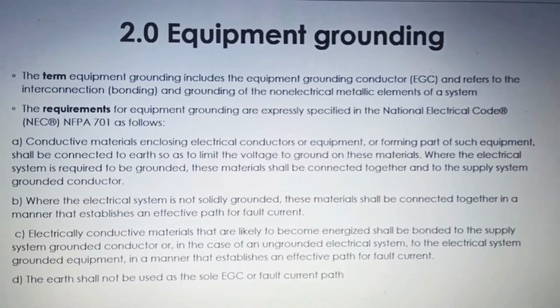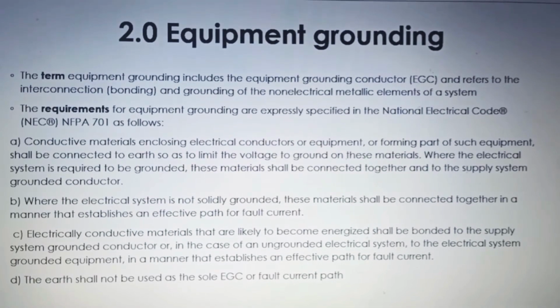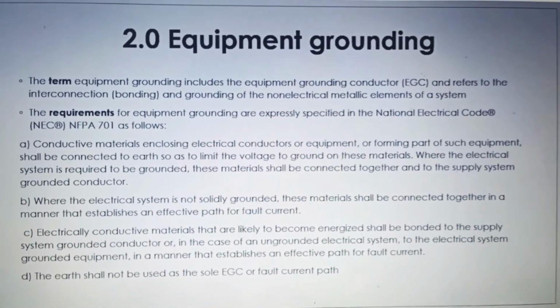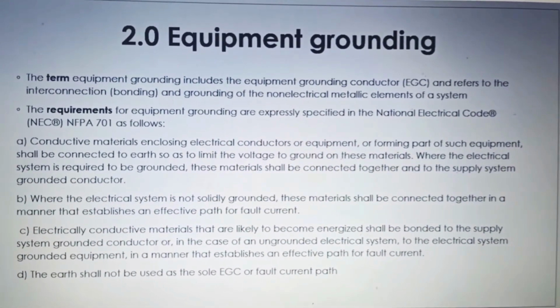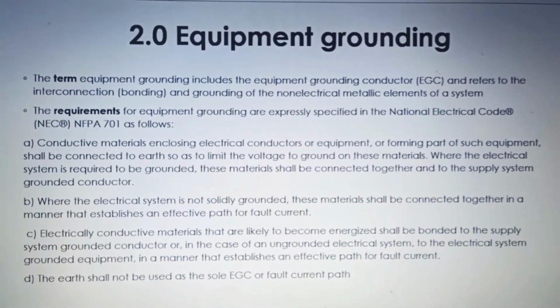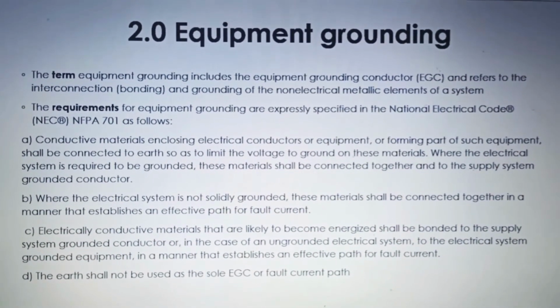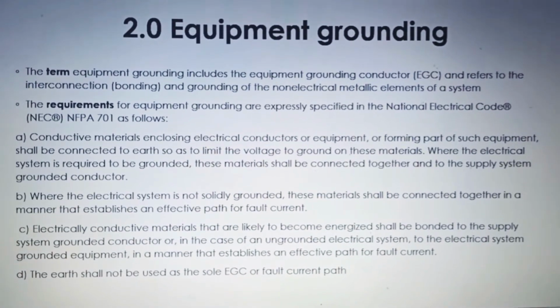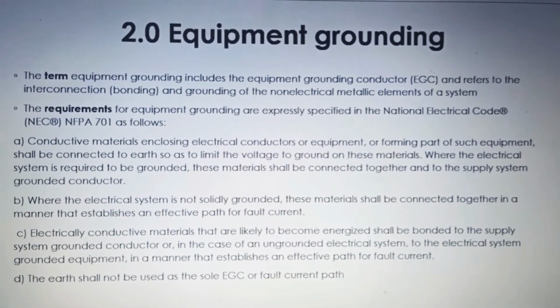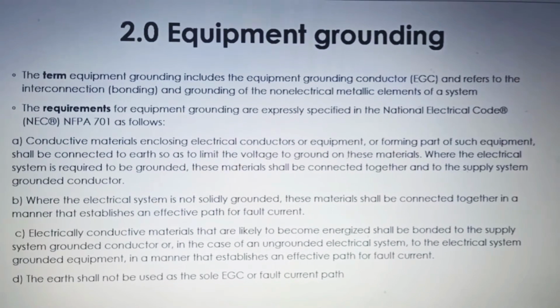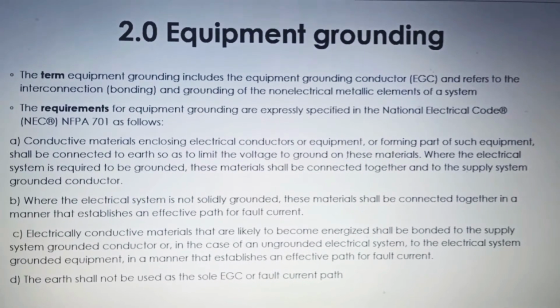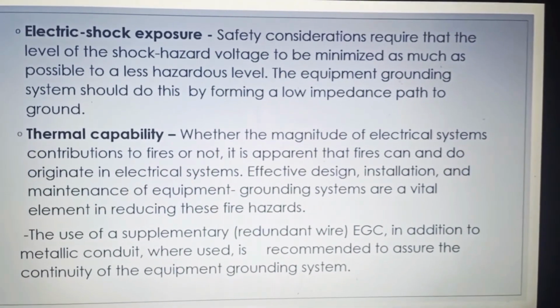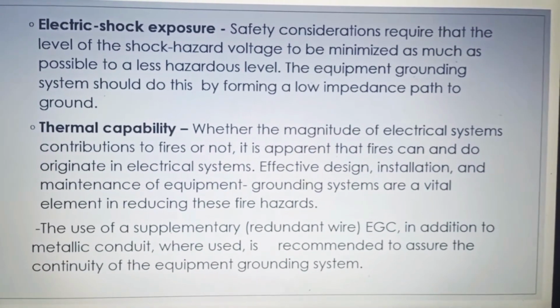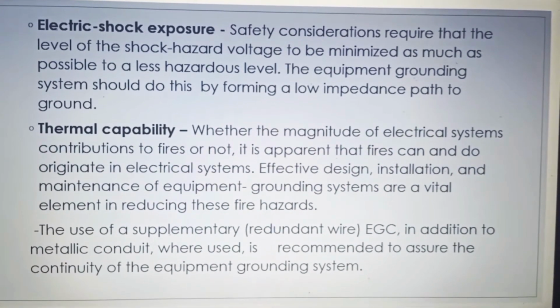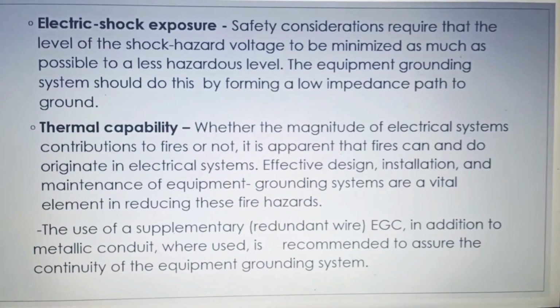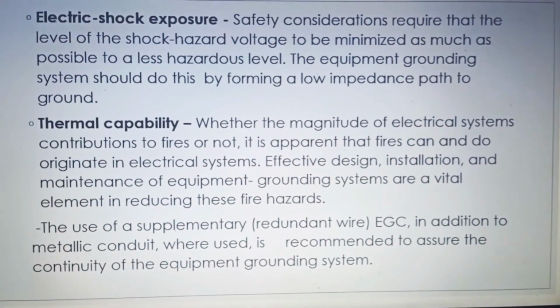Electrically conductive materials that are likely to become energized shall be bonded to the supply system grounded conductor, or, in the case of an ungrounded electrical system, to the electrical system grounded equipment in a manner that establishes an effective path for fault current. Electric shock injuries result from contact with metallic components that are energized, whether intentionally or unintentionally. Effective equipment grounding practice can minimize these personal injuries.